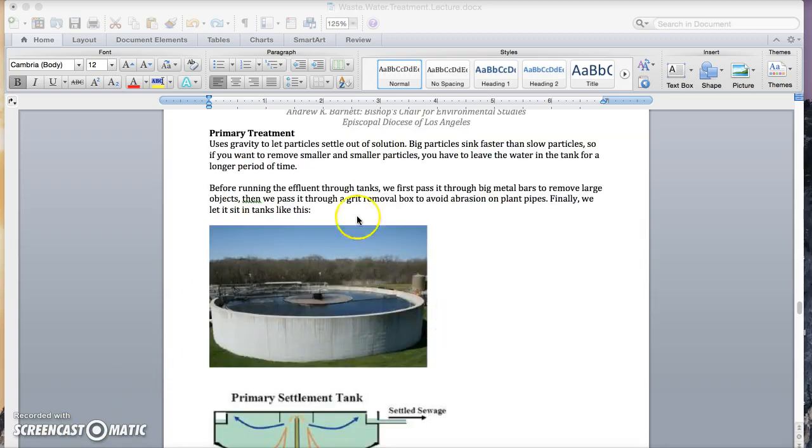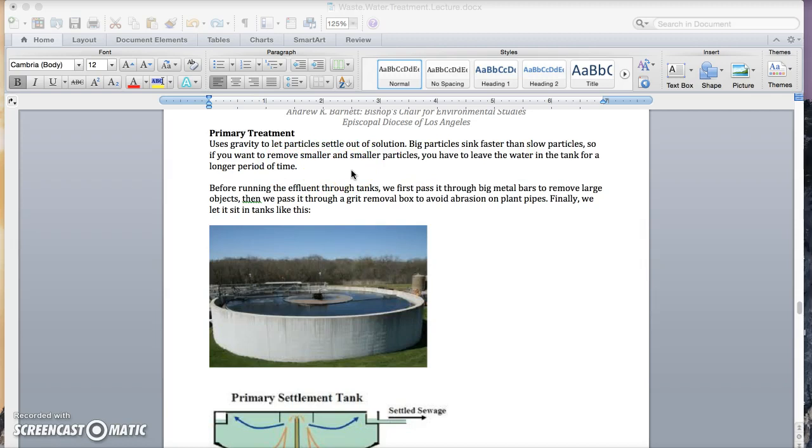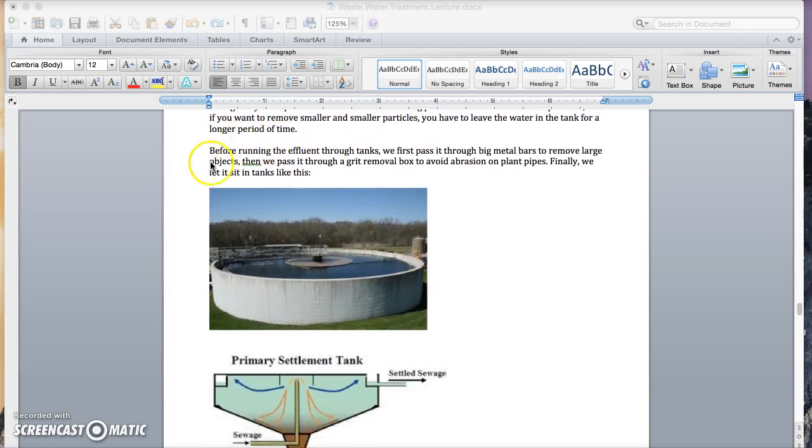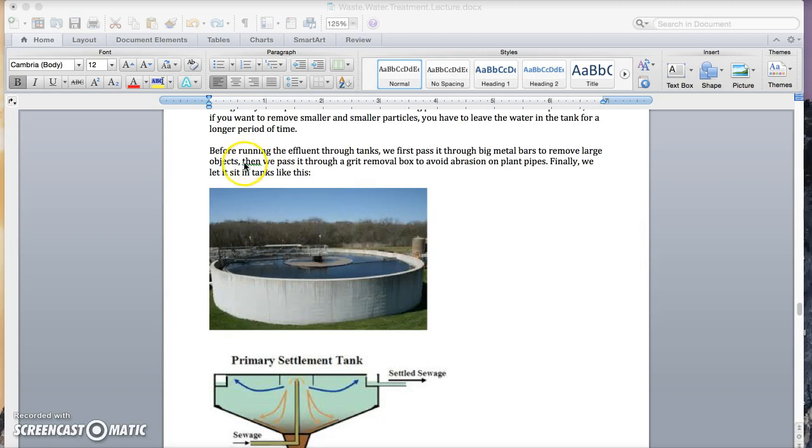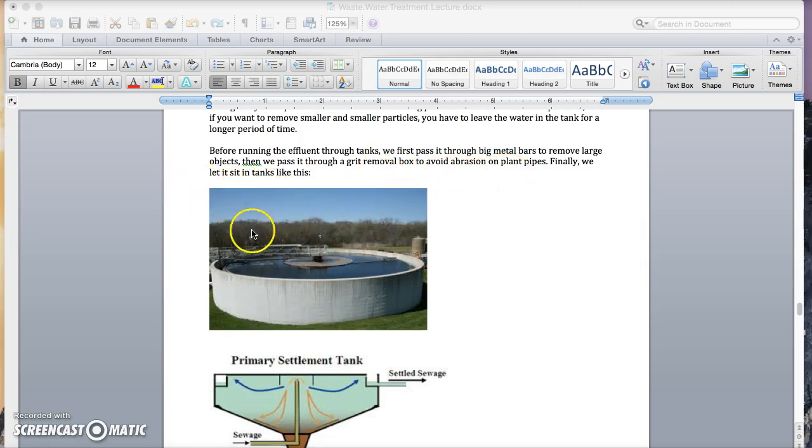In primary treatment, you use gravity to let particles settle out of solution. Big particles sink faster than slow particles. So if you want to remove smaller and smaller particles, you have to leave the water in the tank for a longer period of time. Before running the effluent through the tanks, we first pass it through big metal bars to remove large objects like logs and other big things. Then we pass it through a grit removal box to avoid abrasion on the plant pipes. And finally, we let it sit in tanks like this.